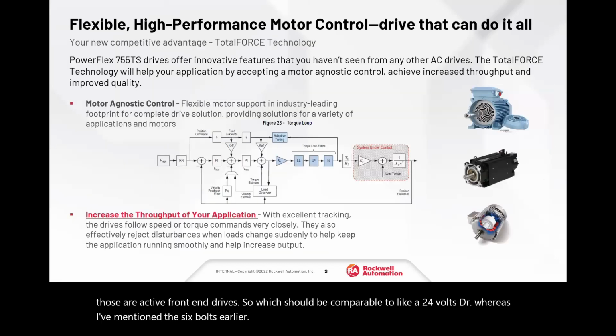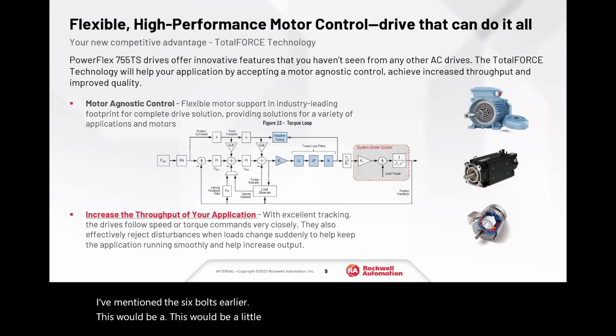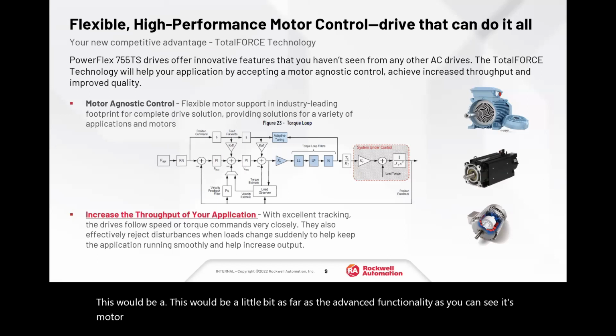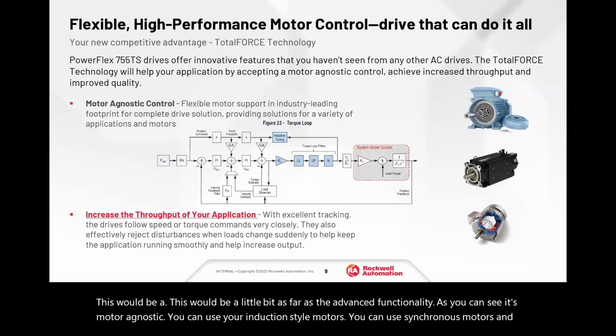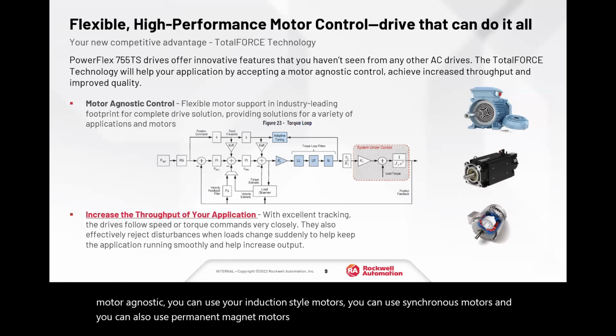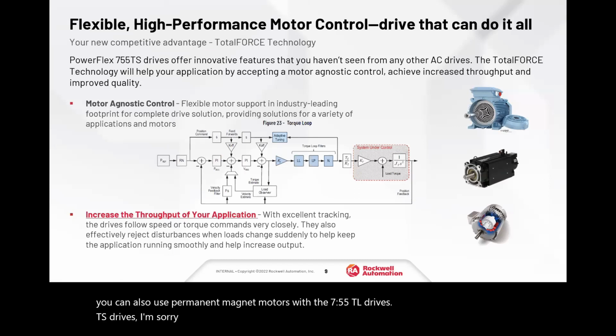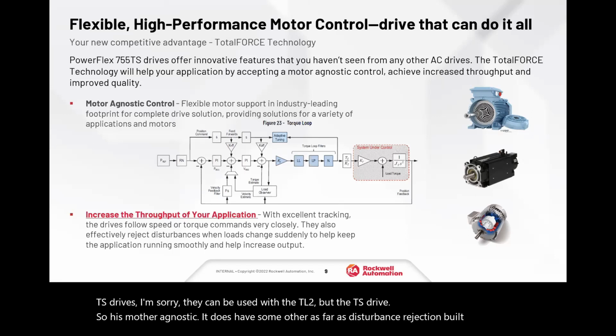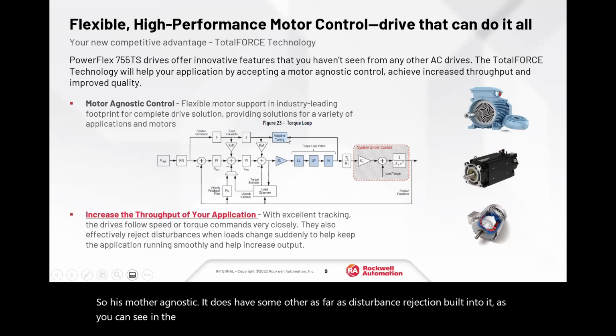This is a bit more of the advanced functionality. As you can see, it's motor agnostic. You can use induction motors, synchronous motors, and also permanent magnet motors with the 755 TS drives. They can be used with the TL too. So it is motor agnostic. It also has disturbance rejection built into it. As you can see in the middle there, there are different parts built into the drive.